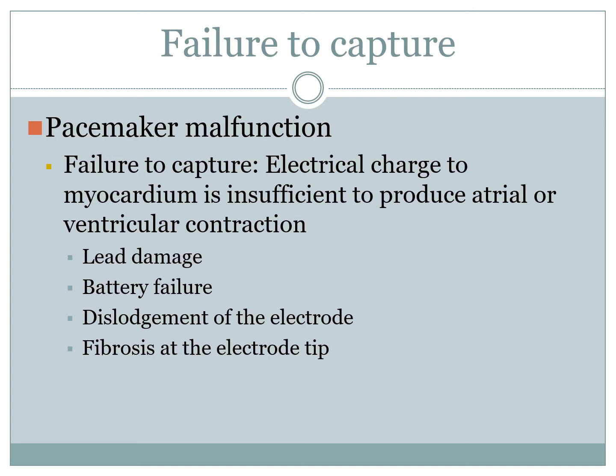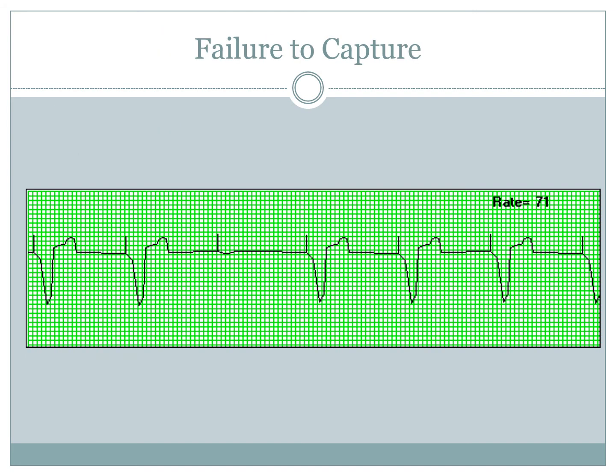Okay, let's see what that looks like on an EKG tracing. Here we go. Now look at the pacer spike. The very first one on the left shows a ventricular contraction and a T wave, and we see another spike and a contraction, and then we see that third spike. Does it result in a myocardial contraction? No. So this is failure to capture, because it definitely discharged an electrical impulse, but it was not captured sufficiently enough to result in a ventricular contraction. Okay, so that is your example for failure to capture.